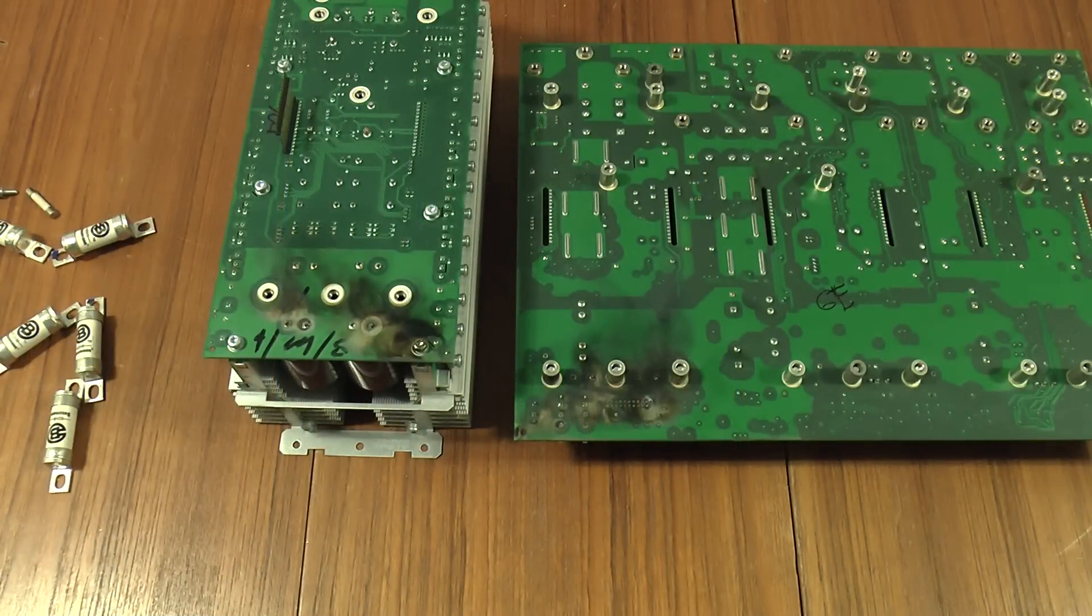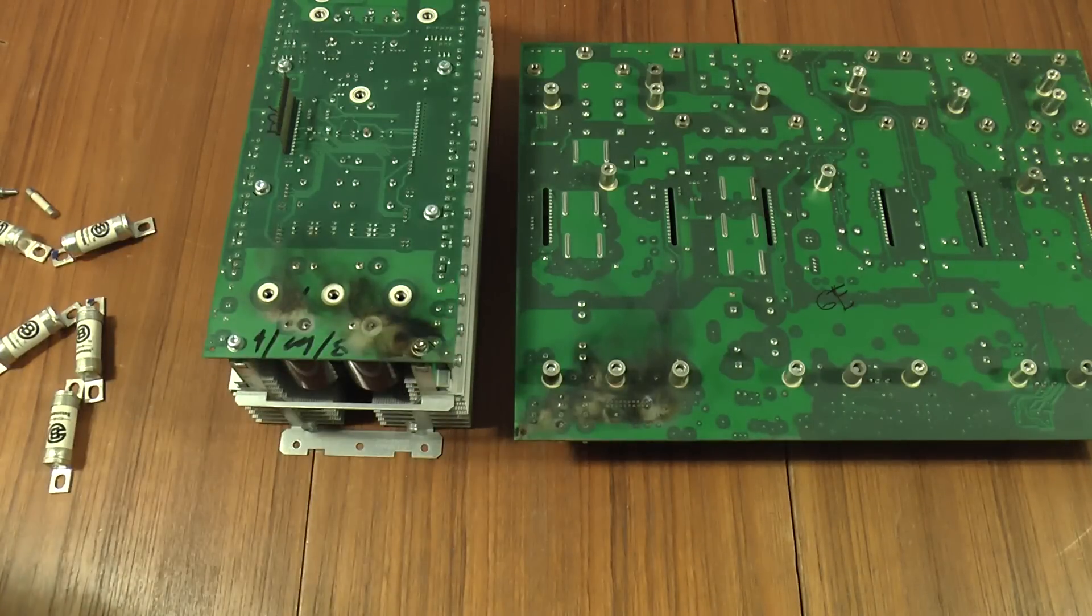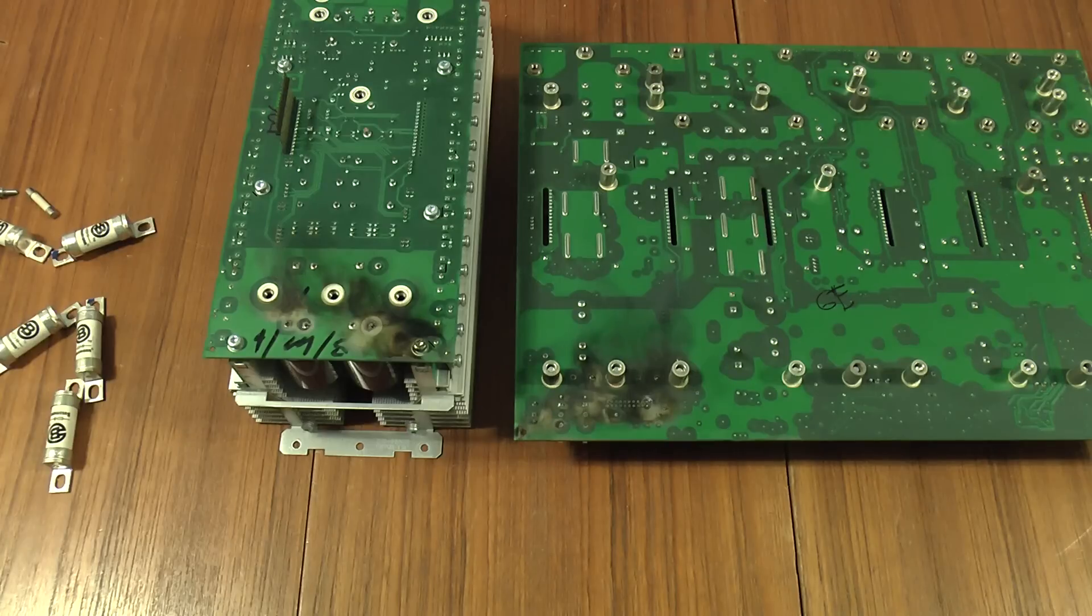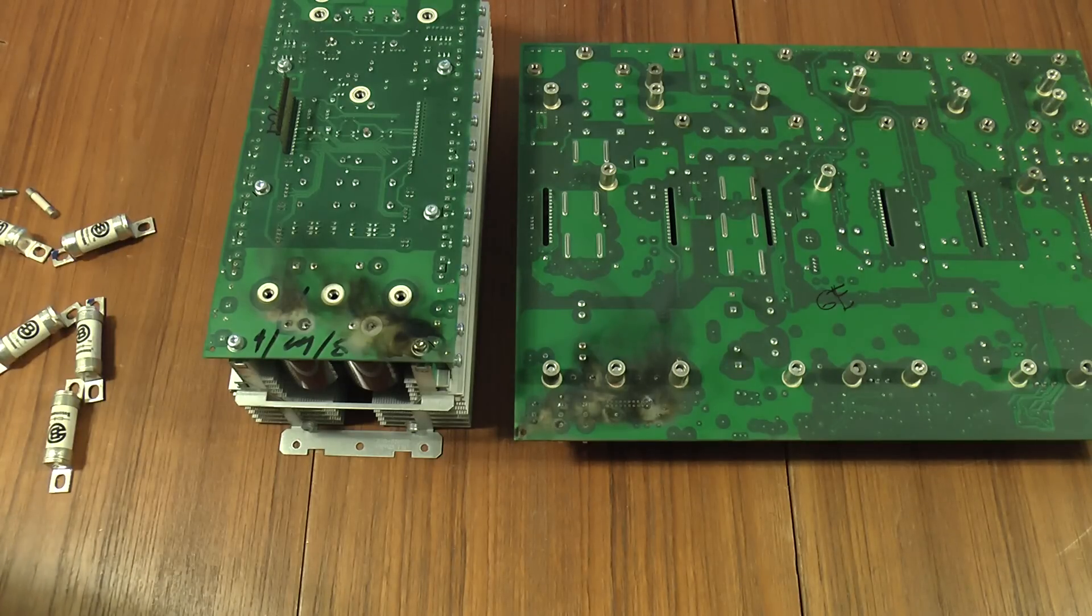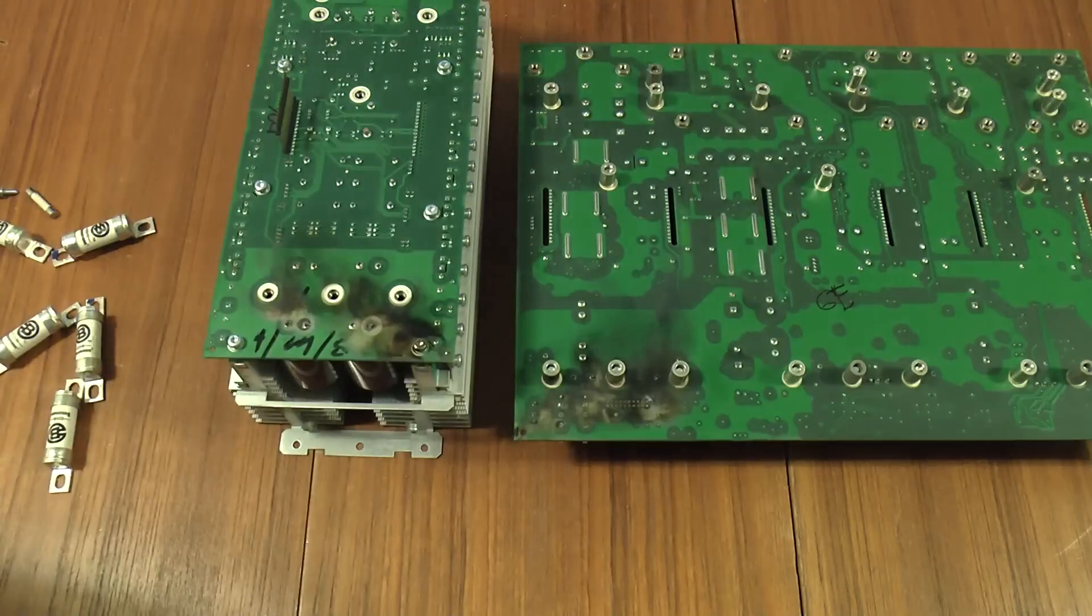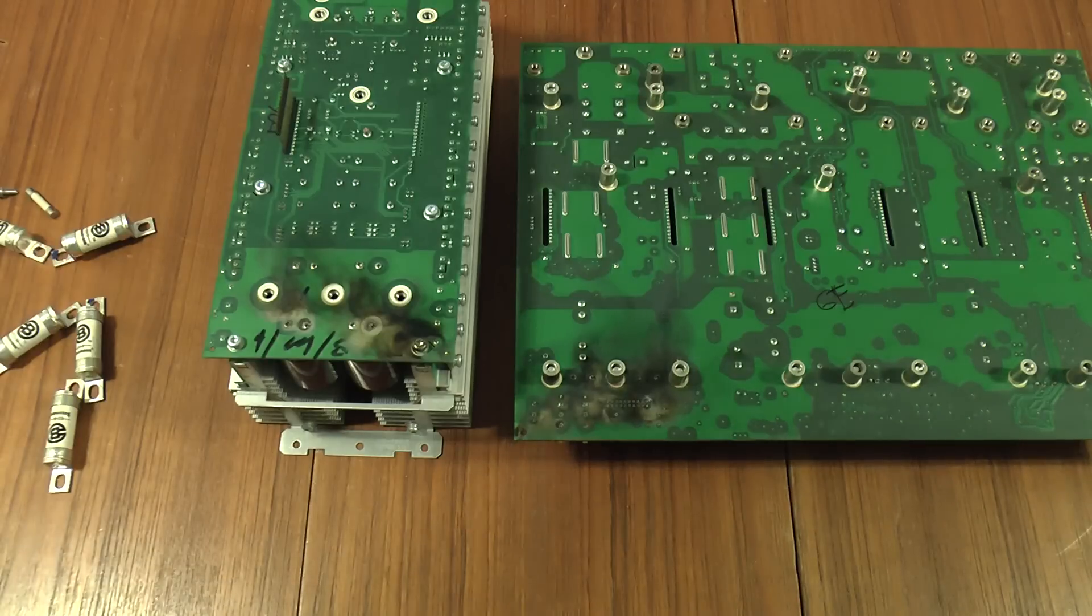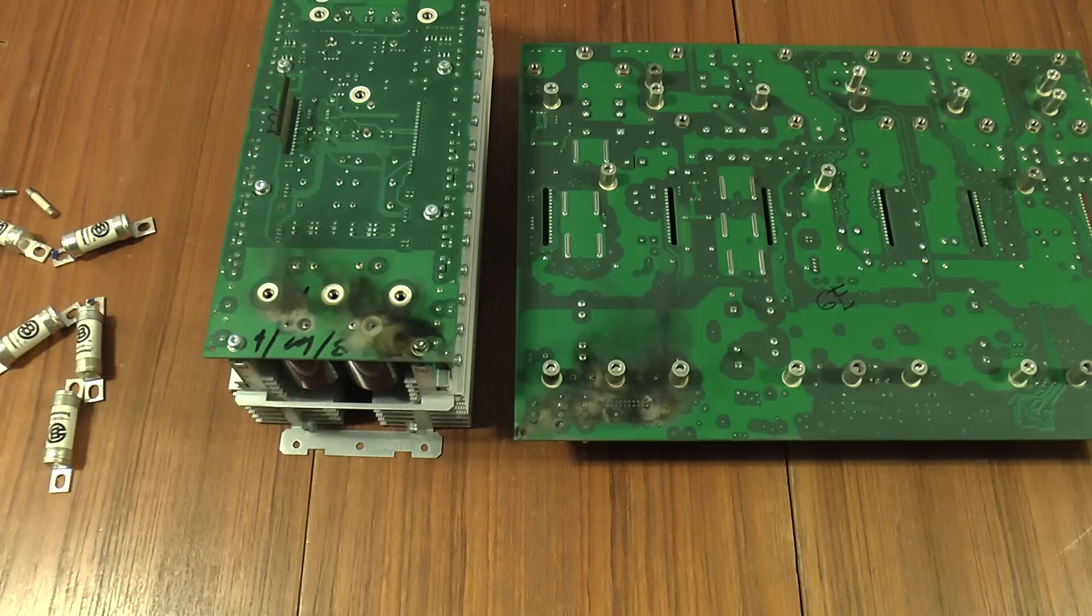I think I found where it failed. That must have gone off with a hell of a bang. This sits there. So it's gone boom basically between here and here. As I said earlier it was in quite a damp area. It wasn't damper than the APC manual recommended. It says it can handle a fairly high amount of humidity. I think it was a combination of it being cold and damp in there is what caused this to happen. Hence the UPS being moved into its own little air conditioned room and having a new power module at the cost of six grand. Still. I'm sure the transistors are fine. 40kW ZVS driver anyone?